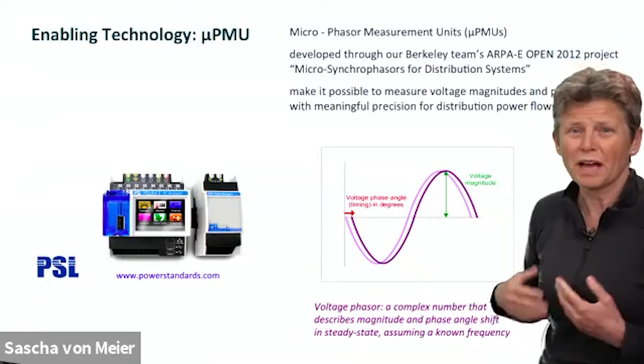And in order to make those measurements, you have to have the same reference clock. So phasor measurement units became an option when there was inexpensive access to GPS timing. And these MicroPMUs, which are designed especially for distribution systems, where you have ever so slight timing differences on the order of degrees or fractions of degrees within the 360-degree cycle, take a very precise timestamp and a high-quality GPS receiver. So that was really the technological innovation here.